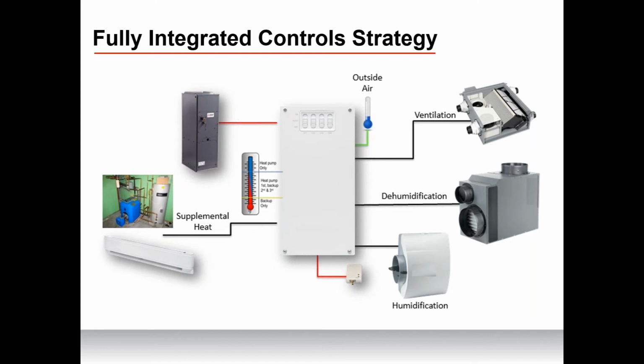If I have a gas backup, let's look at what I can do. Where is my balance point? Where is the most efficient temperature to turn off that air source heat pump and turn on that gas powered system? So if I have a boiler or a furnace, I don't want to turn that on at 40 degrees. I'm still getting great efficiencies out of my air source heat pump. What is that temperature? We need to look at balance point, both economical as well as thermal. Where does it make the most sense to integrate that? And then set that outdoor sensor to only turn that backup heat source on at that temperature. So let's get the most efficiency out of this as we can.